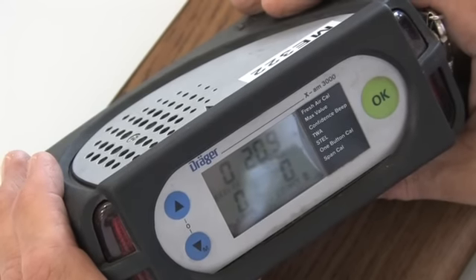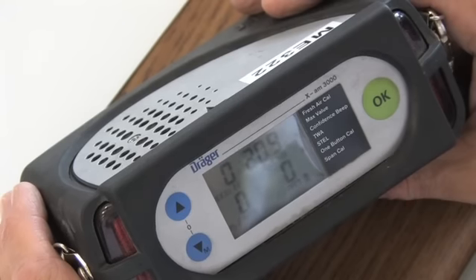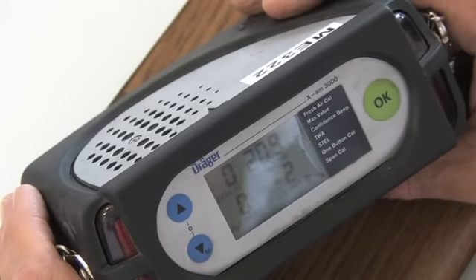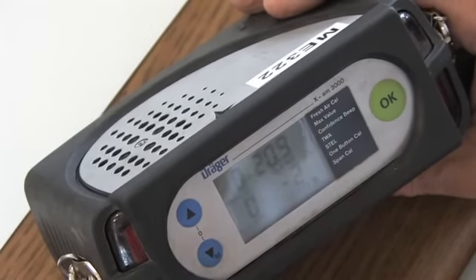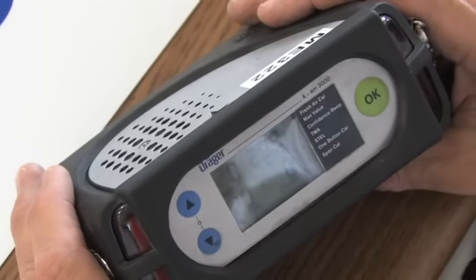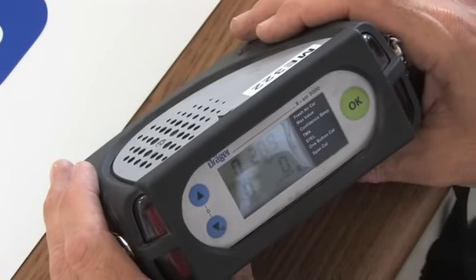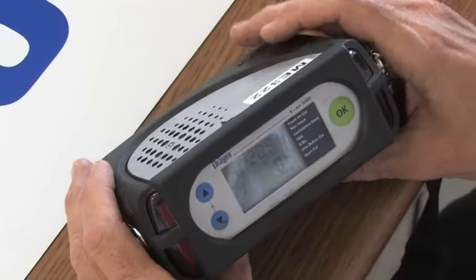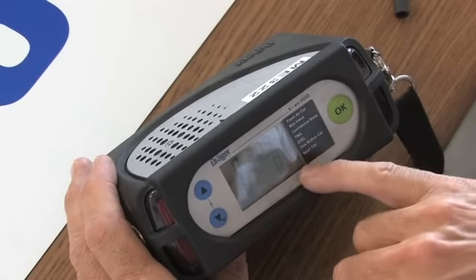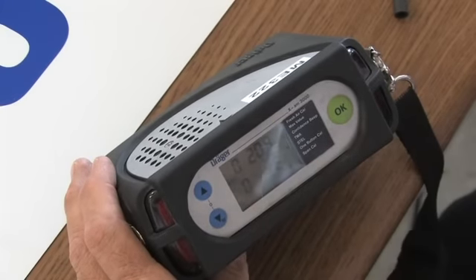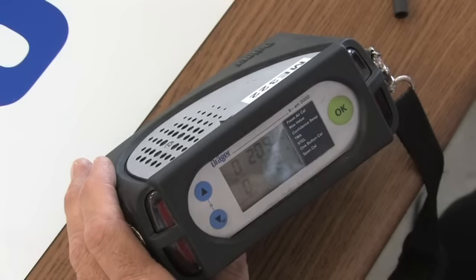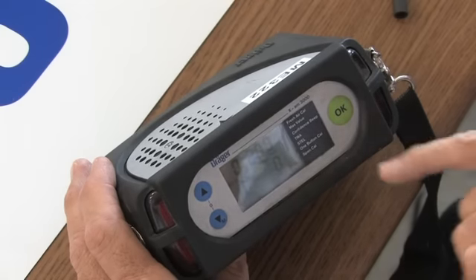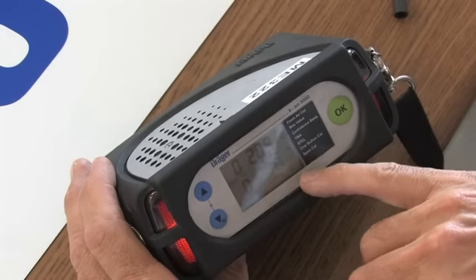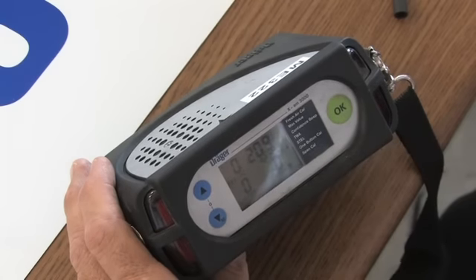So for a firefighter that wants to use this meter, here's what you do. The first thing you do, we have a little bit of drift on our CO, which I don't particularly like. So I'm going to do a fresh air calibration with this meter. That's going to be the first thing I'm going to start. But I've already noticed too that I have a full battery, and the battery is in 1/3 segments. So 33, 66, 99%, or 33.3, however you want to do it. But when you get down to one segment at the bottom, the instrument has to go onto charge.